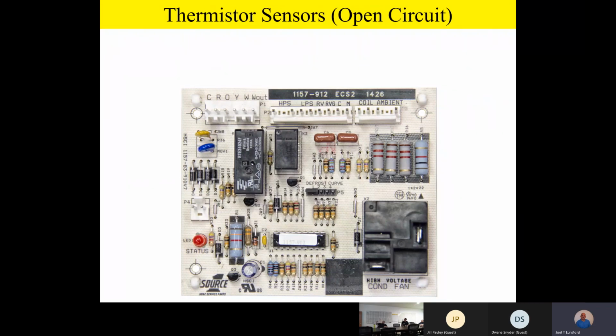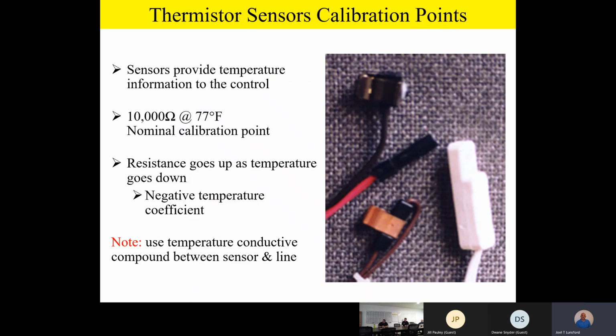Now, we had mentioned earlier that the open circuit voltage, in other words, if I remove the sensors from the board, I should be able to read 4 to 5 volts DC on those sensor pins without the sensors plugged on. Now, once I see that I've got 4 to 5 volts DC and I plug the sensor back on, that sensor is going to start sensing the temperature that it's subject to, whether it's the coil sensor or the ambient sensor. So let's talk a little bit about those sensors. Those sensors actually have a calibration point, and it doesn't matter what sensor you're looking at. On our heat pumps, even though they're packaged a little bit differently, as you take a look at the photo, you're going to notice that there's a white sensor on the right-hand side of the photo. That's actually the ambient sensor. That's the one that just hangs out in the breeze, right?